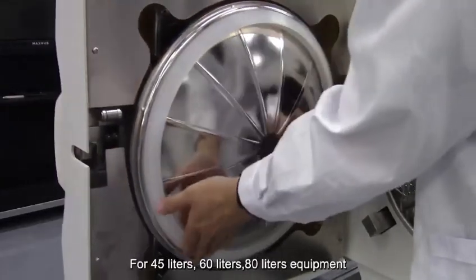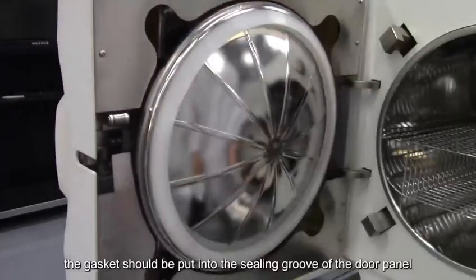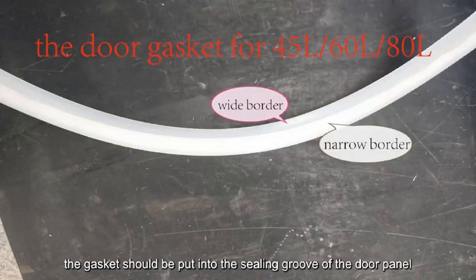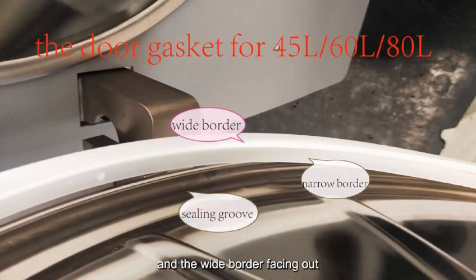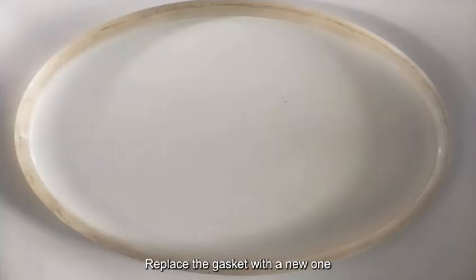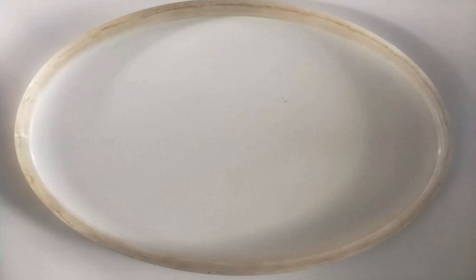For 45 liter, 60 liter, and 80 liter equipment, the gasket should be put into the sealing groove of the door panel with the narrow border and the wide border facing out. Replace the gasket with a new one when it is found to be aged and hardened.